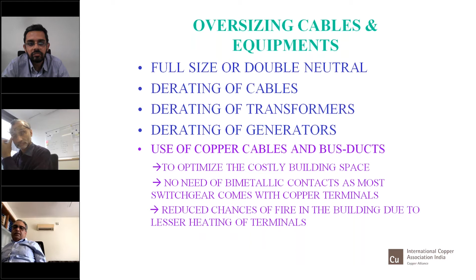Power factor also plays a very important role in the overall scheme of safety and power quality. I think I mentioned somewhere here, yes, that nowadays you should always maintain near unity power factor. You would require lesser size of cables if you use unity power factor, because for a lower power factor the cable size increases. Heating would be less, because heating is directly I square R. While you may be drawing the same amount of power, your I would be higher and the heating would be higher.